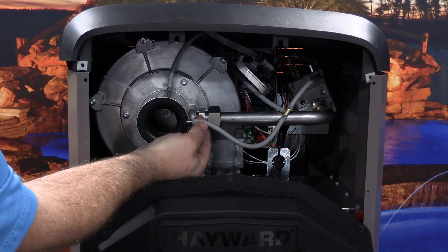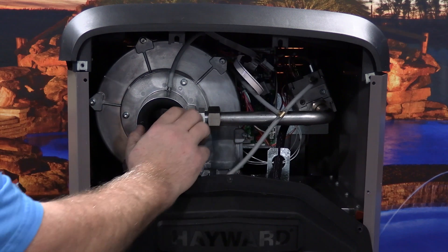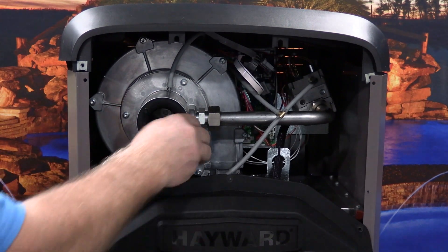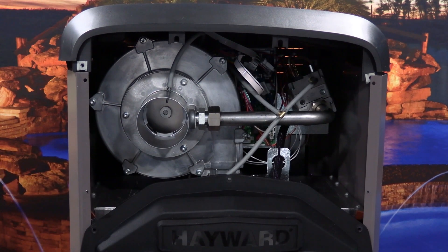Disconnect the silicone tube from the gas air orifice and let it hang to the side. Now, rotate the natural gas orifice a quarter turn clockwise until it stops and pull the orifice towards you to remove it from the combustion blower.